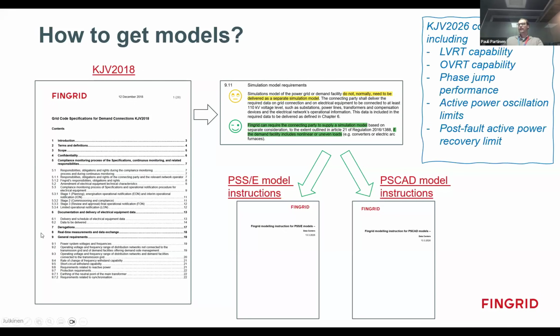And in addition to these new modeling instructions, we have released our new grid code for demand for public hearing. This will introduce significant changes for the technical requirements for demand plants. This will include low voltage ride-through capability, overvoltage ride-through capability, phase jump performance, for example, active power oscillation limits for the subsynchronous band, post-fault active power recovery limit.